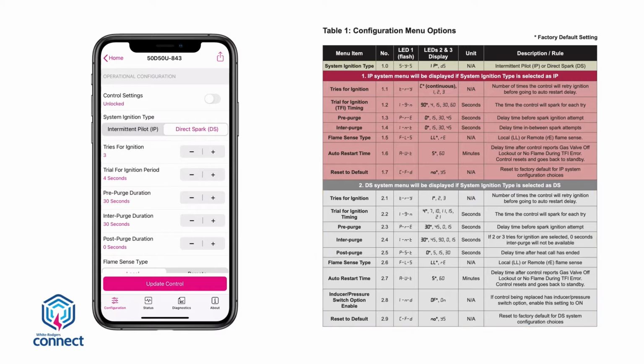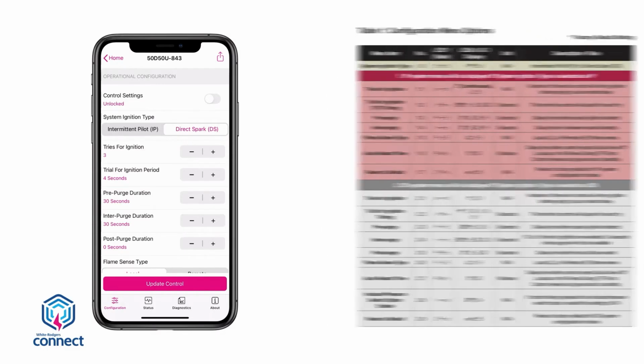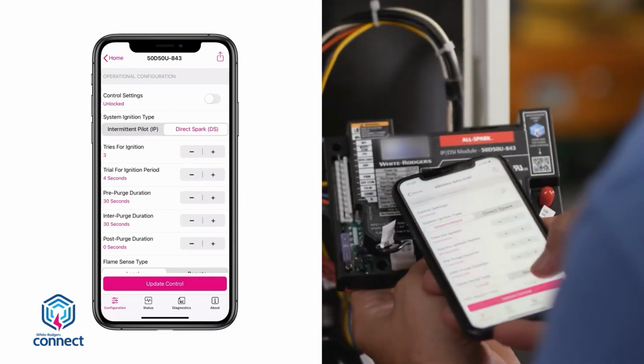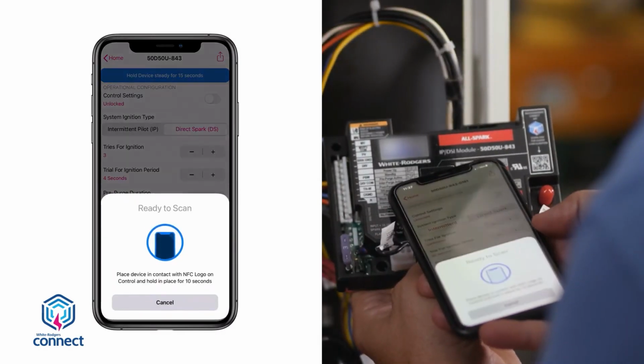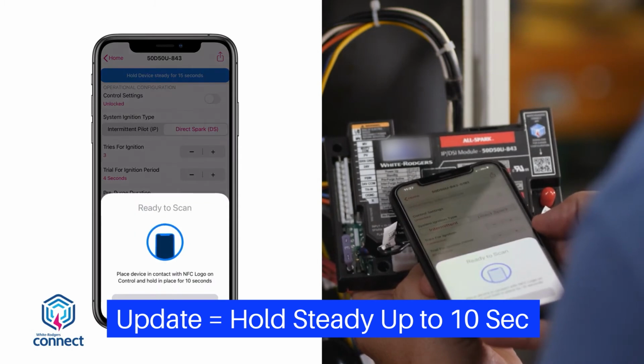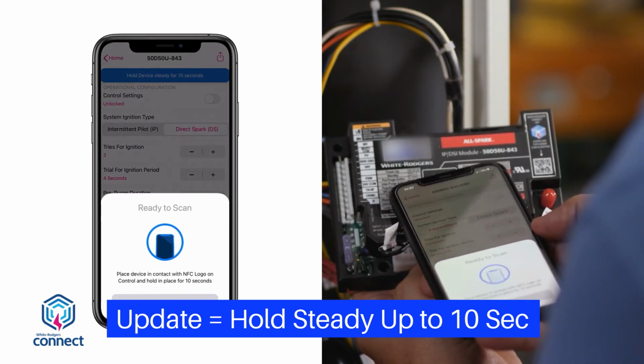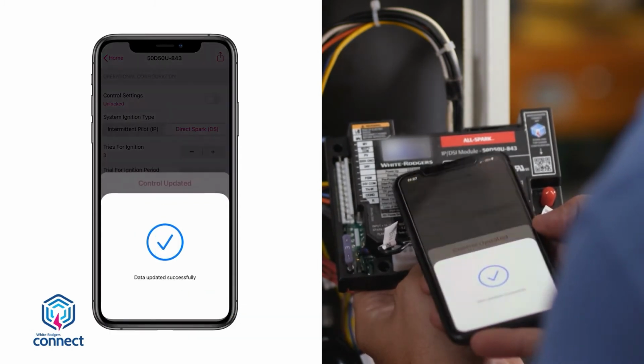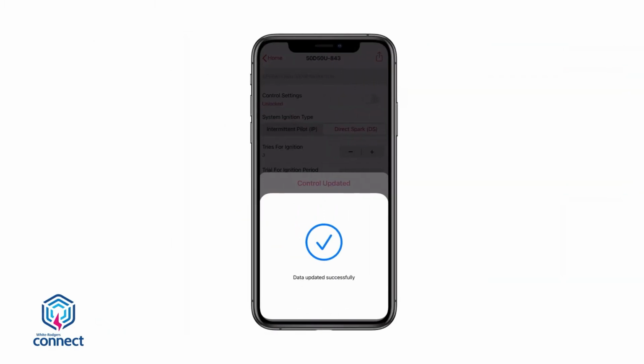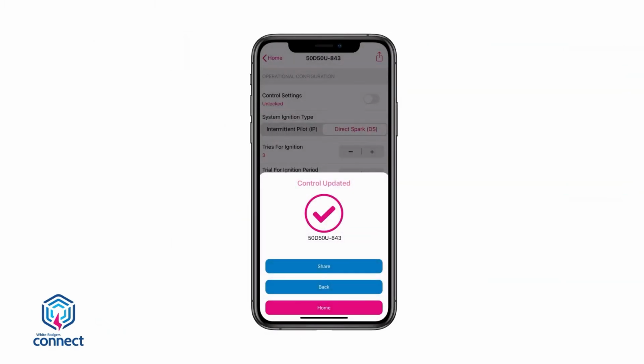Settings can be adjusted to match the existing module. For this application, the factory default matches the existing S8610U control. No changes are needed. If any changes are made, they must be uploaded to the module. Select the Update Control button and again hold the mobile device near the NFC logo. A check mark will display showing the update was successful. The 50D50U-843 is now ready to be installed.